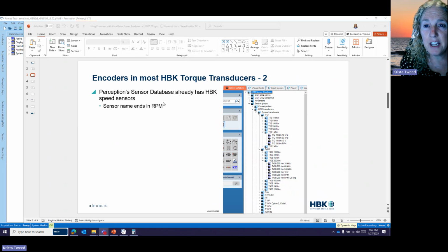Now in Perception, once you've got everything connected, because it is our sensor, we already have that included in the HBM sensor database. So if I go to the sensor database sheet in Perception, and I expand under sensor groups, torque transducers, most commonly with eDrive, people are using T40B or T12. And if I expand one example of each of those, you see in each case, you've got an RPM option. That is the speed sensor that's part of that torque transducer. With the T40, you will see two different RPM sensors. One of those says 128 pulses per revolution. The other one is the 1024 pulses per revolution. And typically people doing eDrive type work will purchase that 1024 to have a better resolution on their speed.